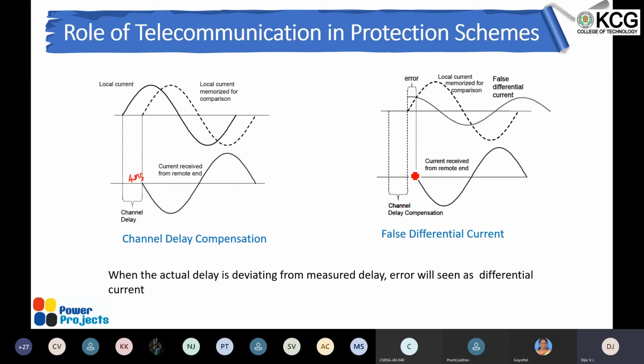So in case the telecommunication people, without informing the protection engineer, installed a device here, maybe to improve the signal reception at the other end, and the protection engineer did not know about it, then this error can happen: an additional time delay of 1 millisecond because of that. Then when the memorized current is compared with the remote end current, there will always be a difference. This difference may be enough for the relay to operate.